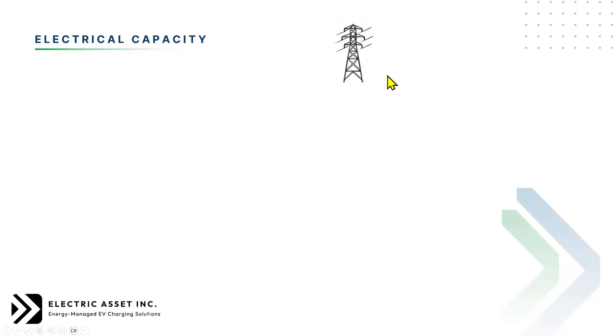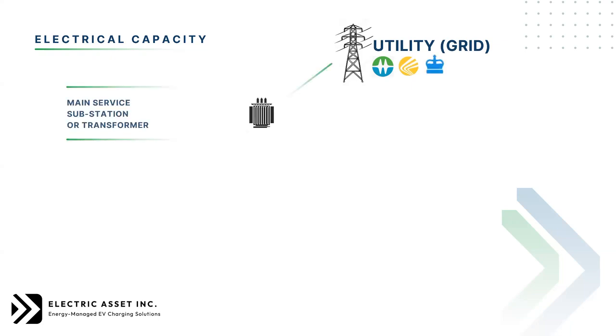When we look at this space for electrical capacity, essentially looking at the layout of a typical strata property, you have the grid - the utility or electrical grid that winds around our province and region, managed by BC Hydro, Fortis BC in the interior, or New West Power in New Westminster. Regardless of the utility you're connected to, somewhere on the property there's a main service, substation, or transformer that powers the entire site and is connected to the utility grid. Between the utility grid and this transformer, there are no meters, no monitors, nothing - basically a raw direct connection of high voltage wires.